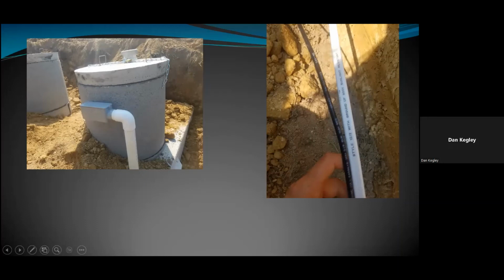Sometimes it'll just have the model numbers. And then if there's model numbers there, as an inspector, we have to go do some research and find the manufacturer, enter the model number, and then find the specs to figure it out, if they don't know, or if we need to verify. But in this particular case, these two are acceptable to be installed for the power wire, the high voltage wire and the low voltage wire.